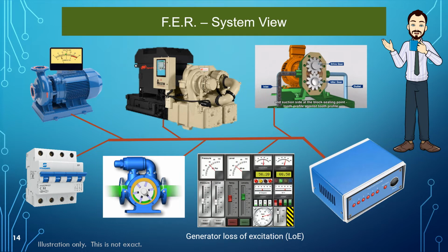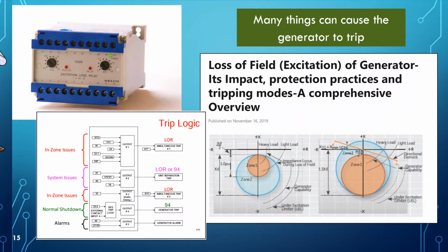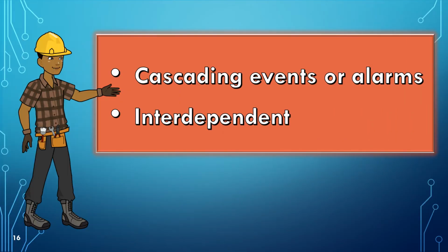The FER systems view. Here are several pieces of equipment. Any one of these can trip and cause the generator to fail. 6 inputs are provided for this FER, and they interact. You have what you call cascading events or alarms. They are interdependent. One oil pump trips, something else is going to fail. A cooling fan or an extractor fan fail, something else will fail. When a circuit breaker trips, many other things will ripple through the system and cause the generator to fail.